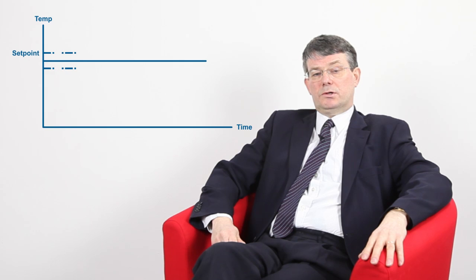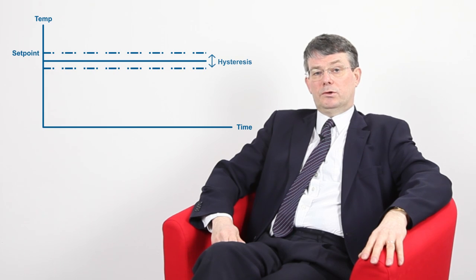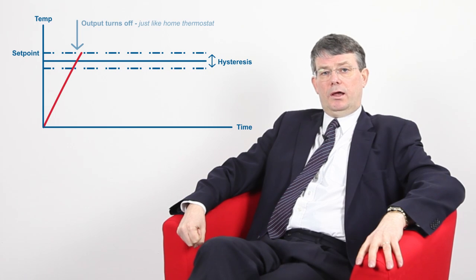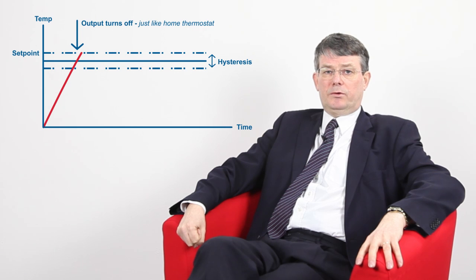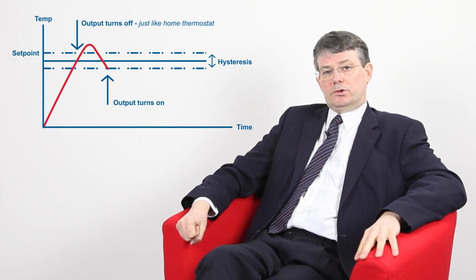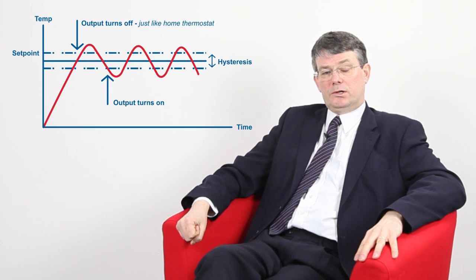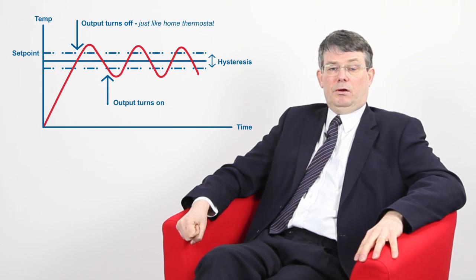We've seen that proportional control will give better stability in the process, so you might wonder why anyone would ever use on-off control. A proportional controller must always be tuned to the process, and this can be a little bit daunting for users. If the process doesn't require a high level of stability, the simplicity of on-off control can sometimes be attractive. Unlike proportional control, on-off control only has a maximum of one parameter to adjust — this is the on-off differential.